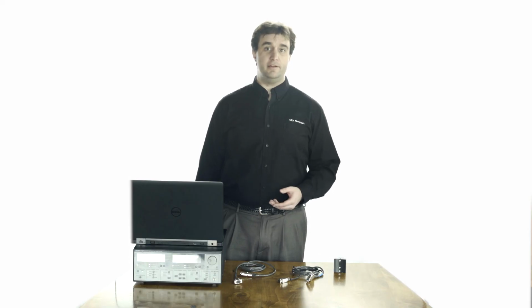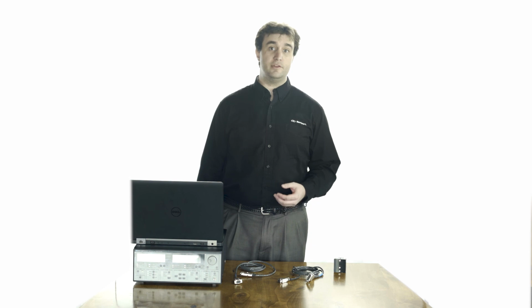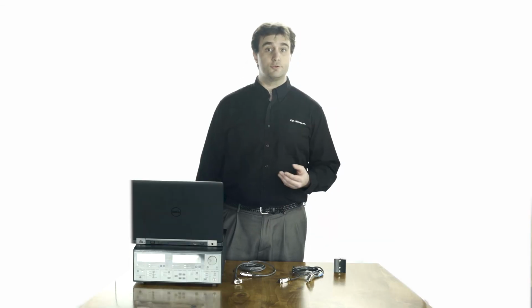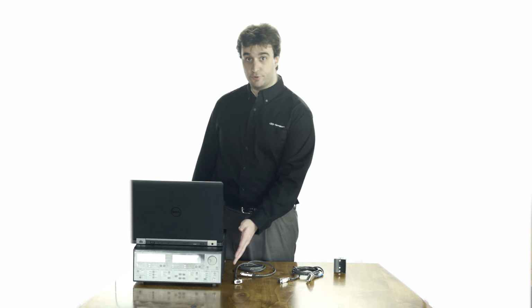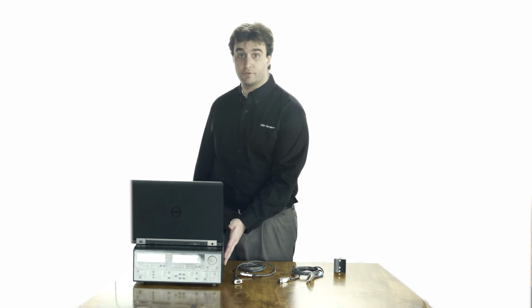When collecting the LIV data, the LDC 3726 steps through a user-defined range of current at a user-defined step size, which determines the number of sampling points. The light intensity, drive current, and voltage are measured directly by the LDC 3726.